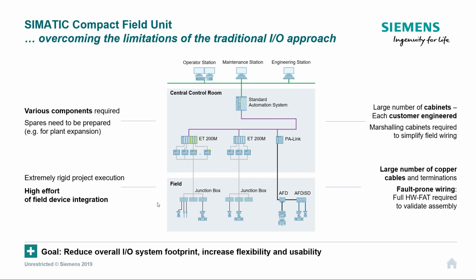If we have a look at your plant, there's various things you've got to do. So here we've got an operator station, maintenance station, engineering station, all connected via Ethernet down to my automation station. This might be a 410 automation station, and then out of here we've got our Profibus DP cable, which is purple, connected to various forms of remote I/O. So here we have some standard I/O, milliamps maybe, with some safety I/O. We need to go out to junction boxes in the field.